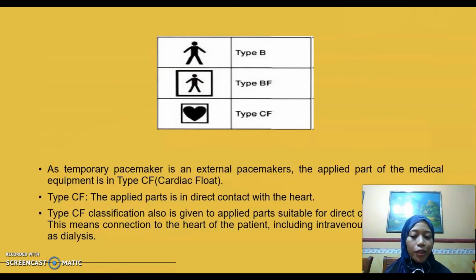As a temporary pacemaker is an external pacemaker, the applied part of the medical equipment is of type cardiac floating, which is CF. A CF applied part is in direct contact with the heart. It is given to applied parts suitable for direct cardiac connection. This means a connection to the heart of the patient, including intravenous connections such as dialysis.